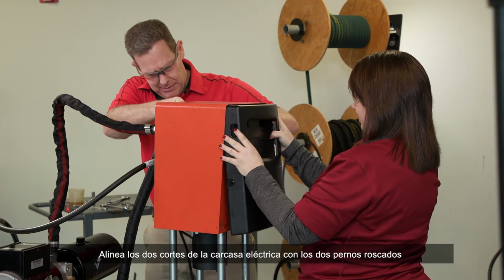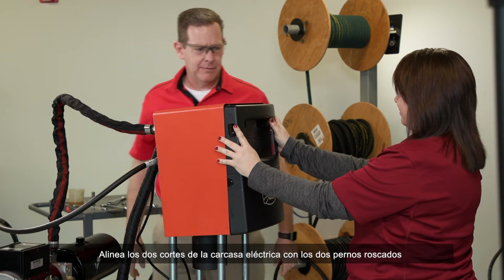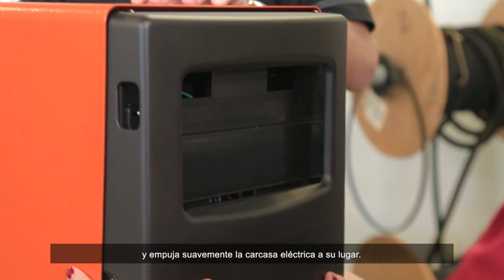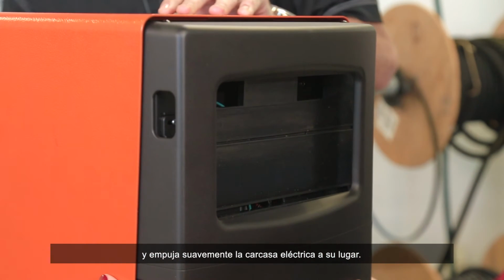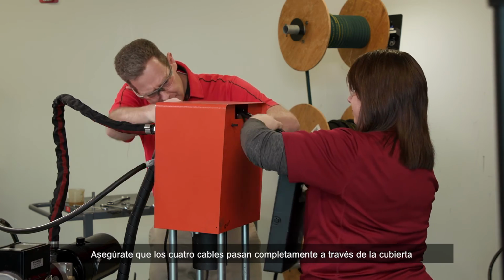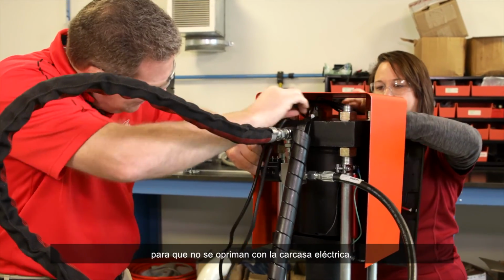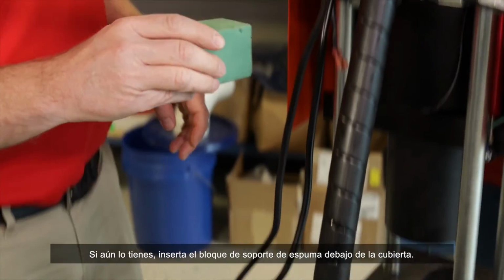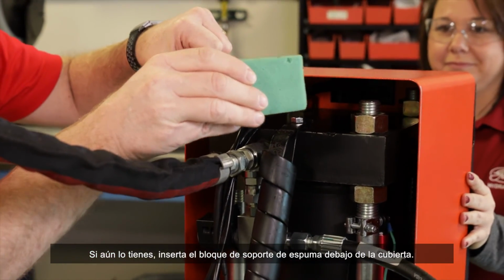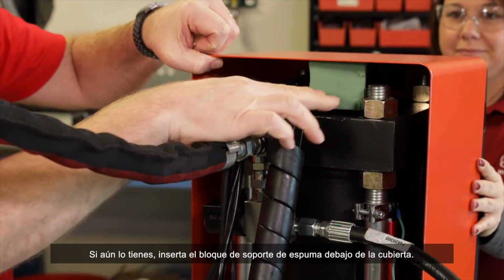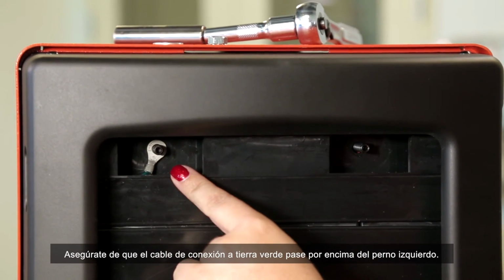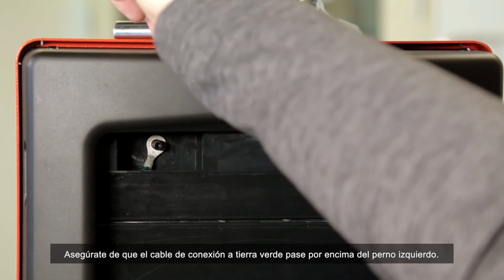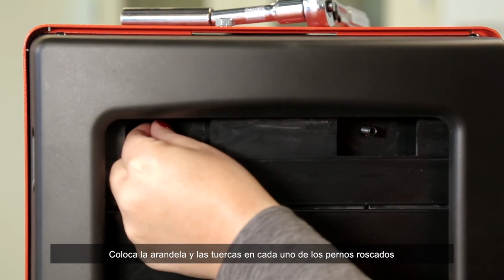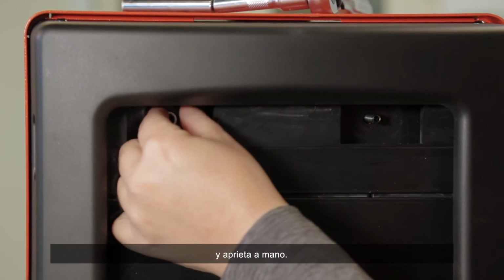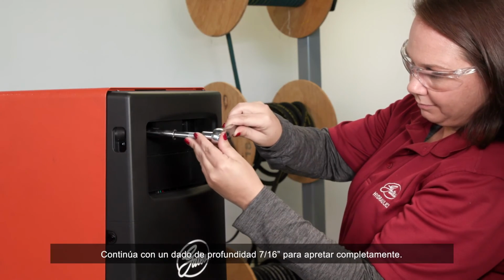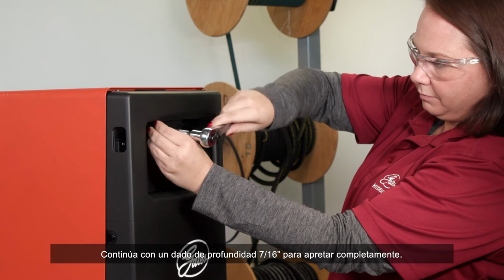Align the 2 cutouts on the electrical housing with the 2 threaded studs and push the electrical housing gently into place. Be sure that the 4 wires are pulled all the way through the shroud so that they aren't pinched by the electrical housing. If you still have it, you can insert the foam support block under the shroud. Ensure that the green grounding wire goes over the left threaded stud. Add the washer and nuts on each of the threaded studs and hand tighten. Then follow up with a 7/16 deep socket to fully tighten.